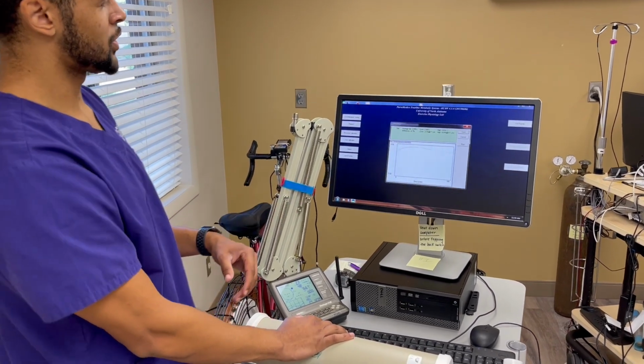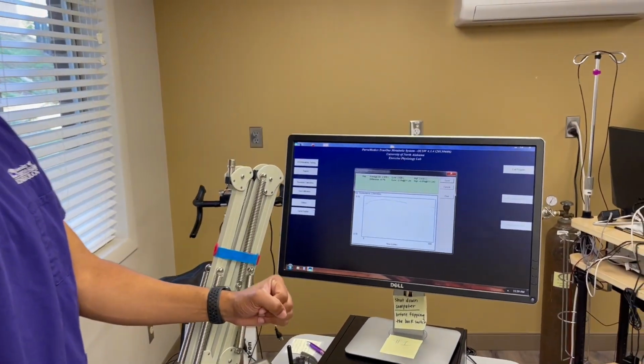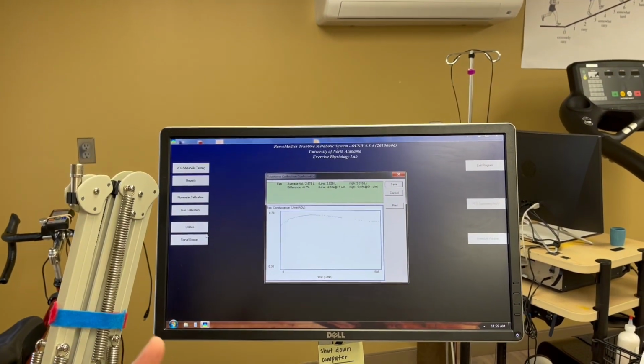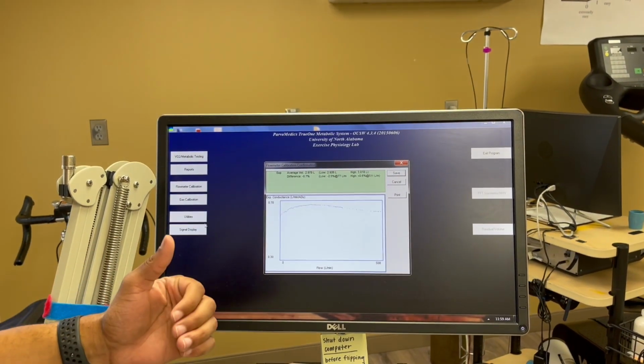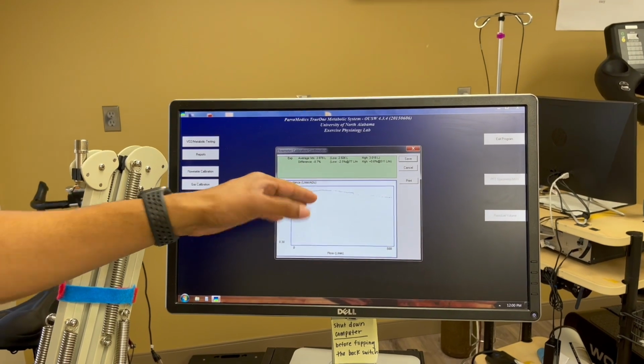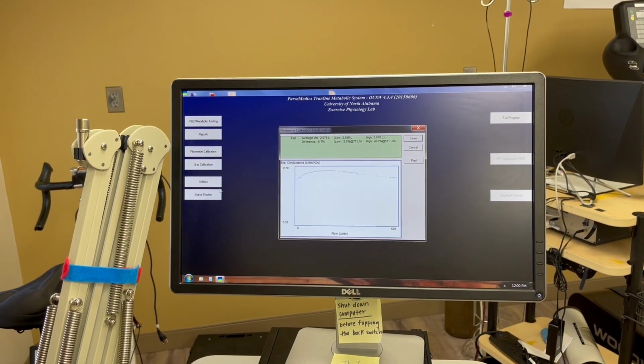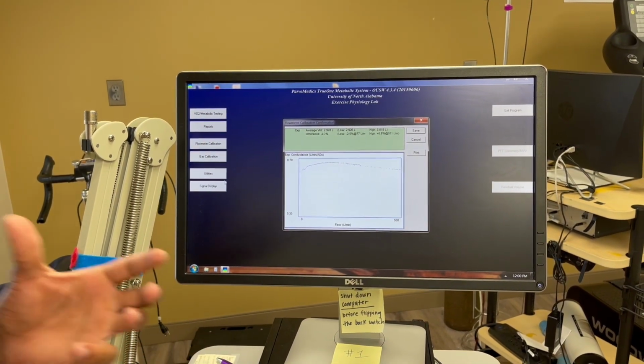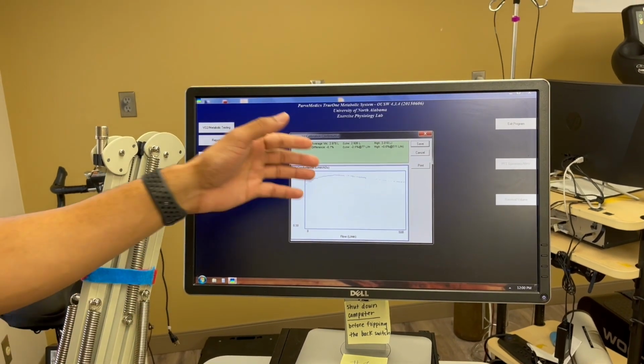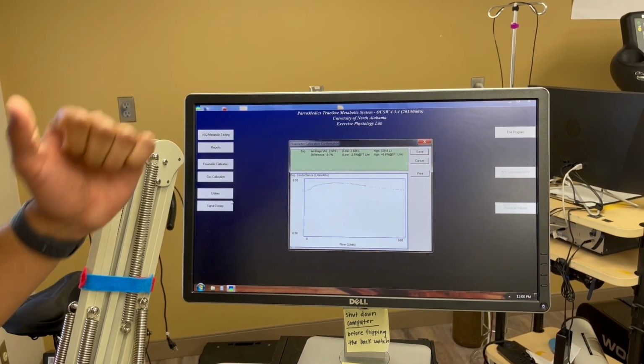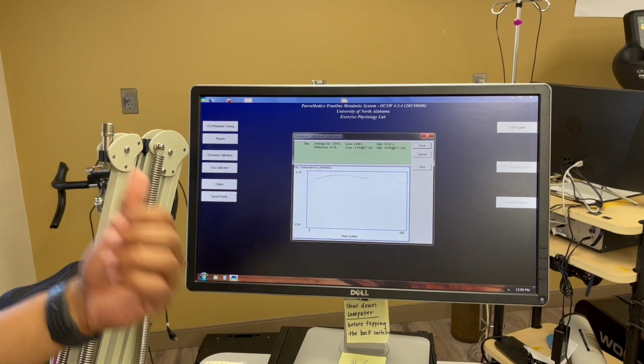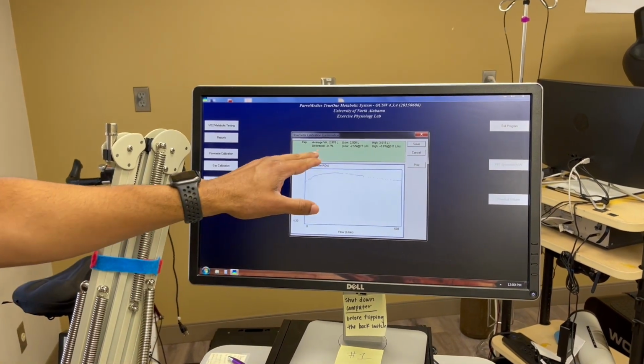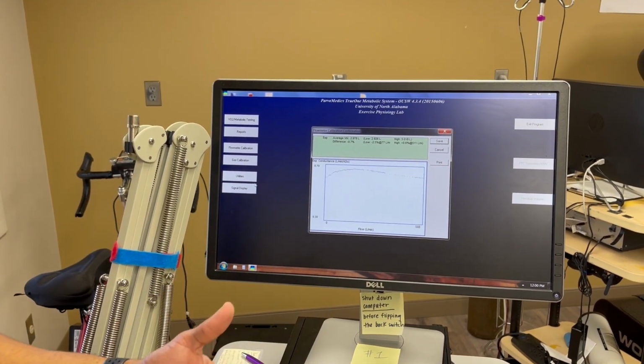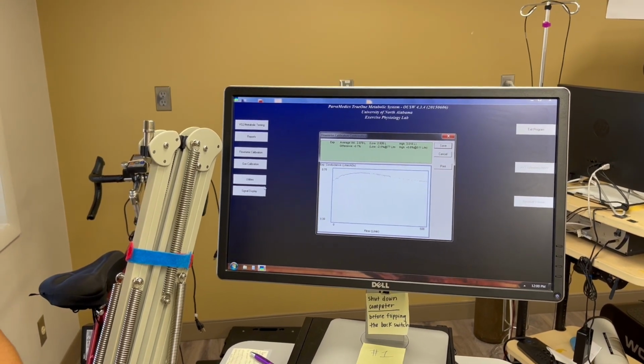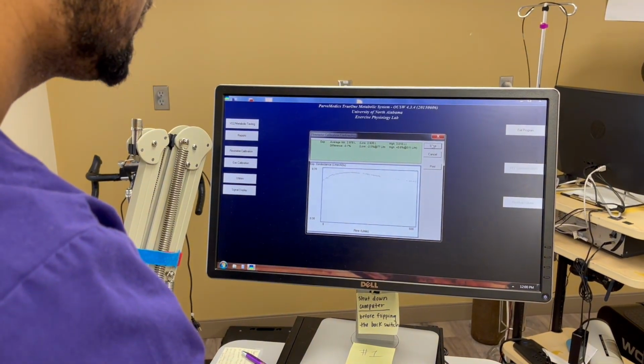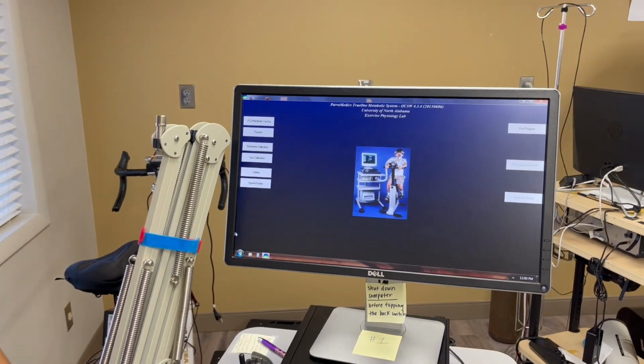So once all the lines go, you'll come back to your calibration screen. It will tell you what the results are. The only thing that you really need to pay attention to is the difference. Same as the gas cal, we want to make sure that that difference is within 1 at all times. That just means that this time calibration was 0.7% different than the last time that you calibrated it. Again, the sign doesn't matter. It can be positive or negative. Once you have that and you're calibrated, all you have to do is hit save and you're good to go.